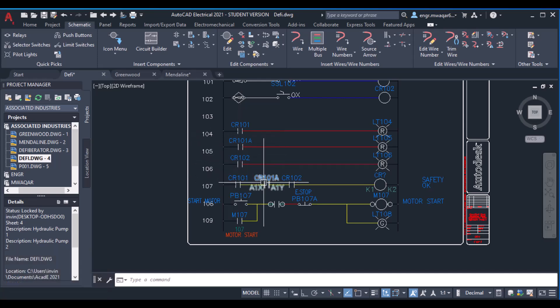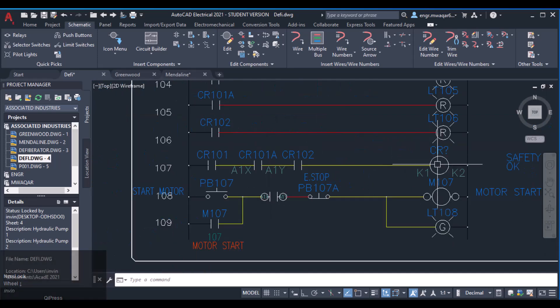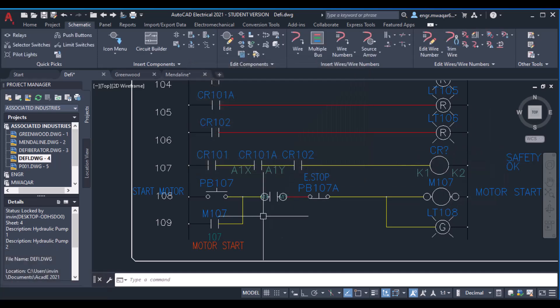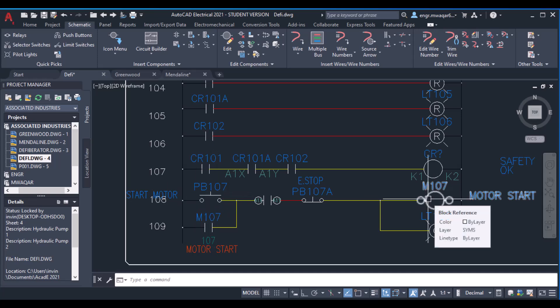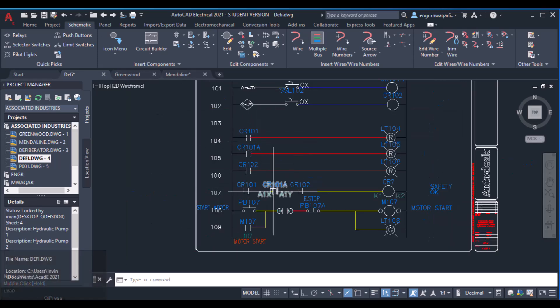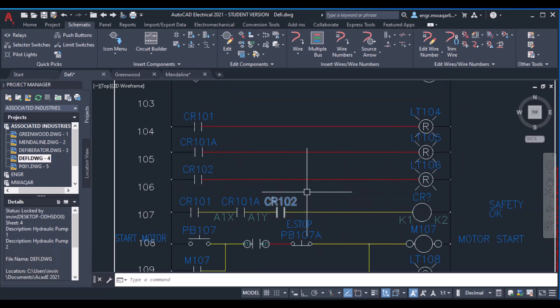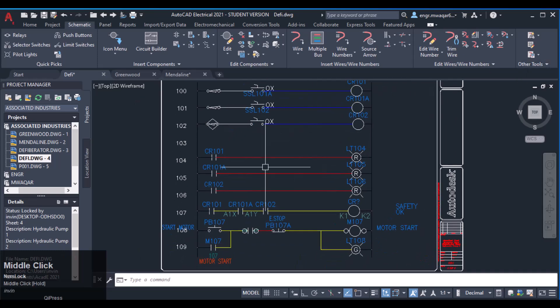Whenever these three relay conditions are all okay, this contact will operate. When all three contacts operate — meaning all three conditions are fine — they will activate another relay I created for safety purposes. This safety relay operates its own contact, which is a sibling contact from the same relay coil. When the operator pushes the button, the motor coil operates and the motor starts running. All three relays must operate to switch on the motor; otherwise, it will not run.